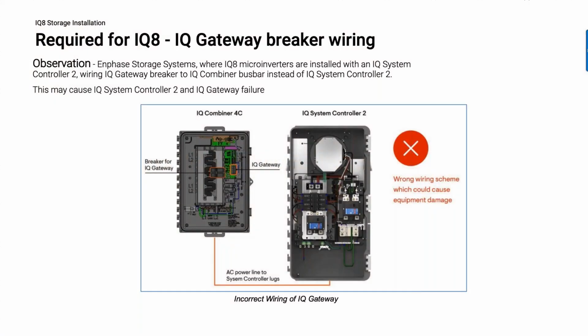Now this again relates specifically to IQ8 systems that you're configuring in backup mode. So you're going to have a system controller, and then you have IQ8s. When you are installing IQ8s in a backup configuration, you must rewire the gateway to be powered off of the common bus of the system controller. That's this bus right here.